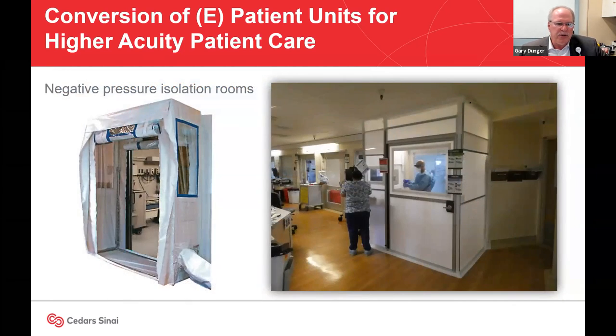Other facilities do things a little more simply. This facility on the right built an anteroom, a negative pressure anteroom, just taped onto the outside of the existing patient room. That's great if you have the space to do that, but if this room opened into a regular corridor, that might not be an option.